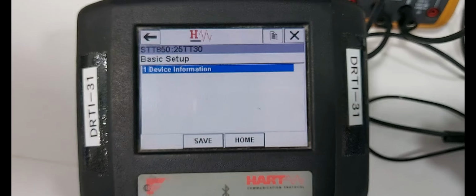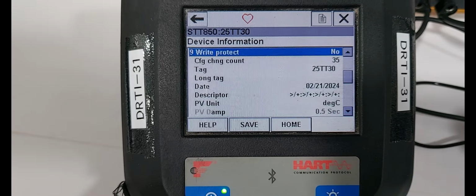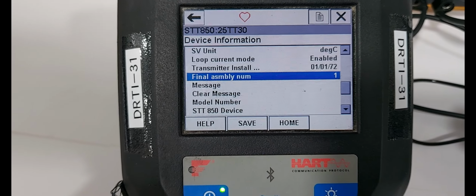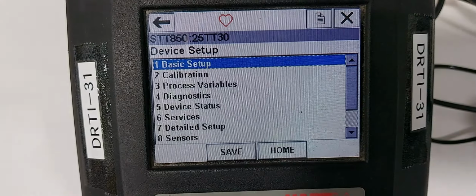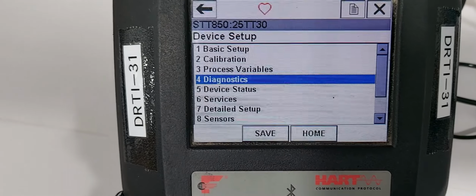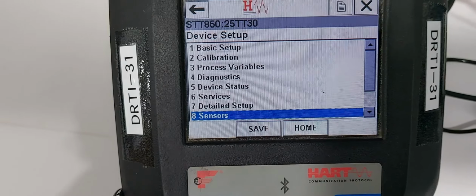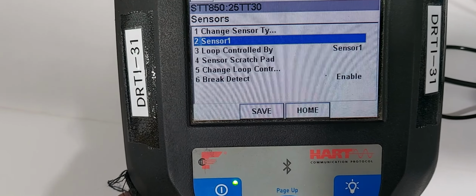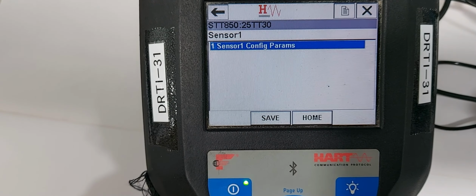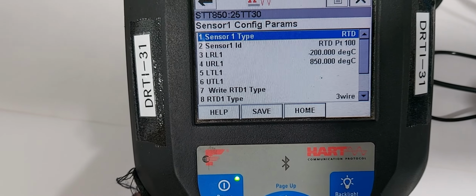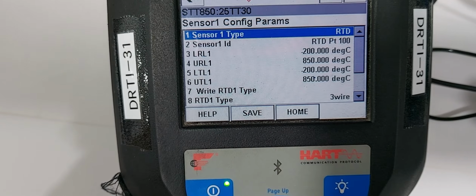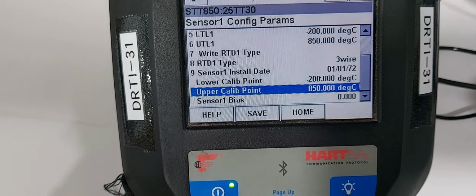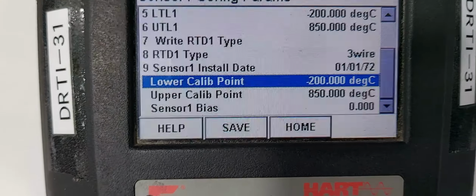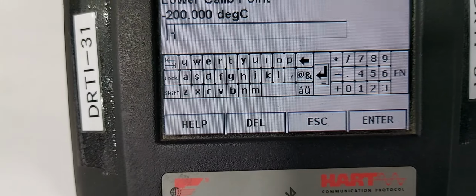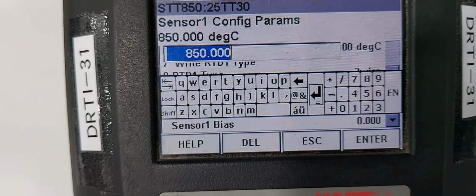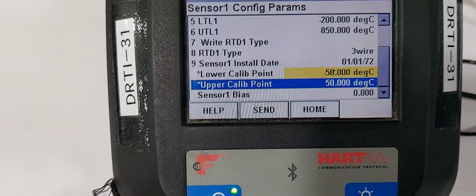Next we are checking the basic setup, device information, and checking the calibration points. First we are checking the LRV and URV points. That is working fine. Next we are checking the calibration point. The calibration point is available. Select sensor 1 area number 2 and sensor 1 configuration number 1 and check the LRV and URV values. And this is a calibration point. The manufacturer actually assigned the calibration point wrongly. Next we are changing the calibration point from here to minus 50 degrees. The upper range calibration point is 50 degrees. Then press enter and send.